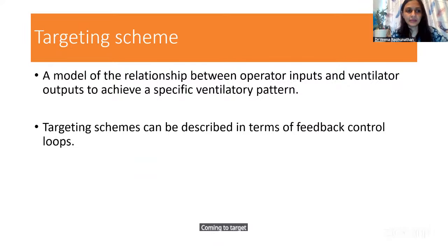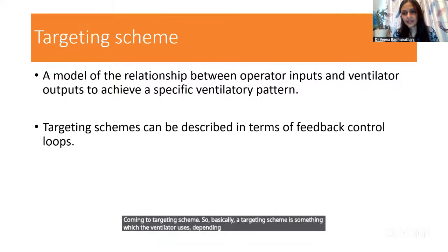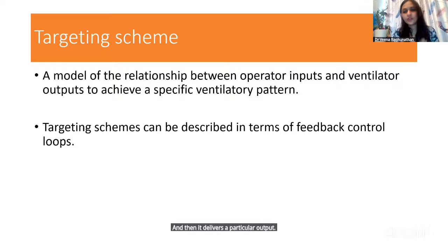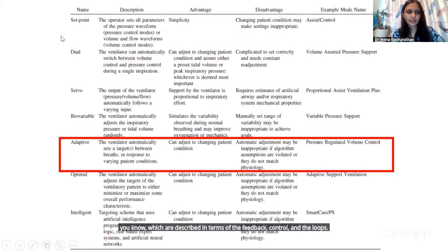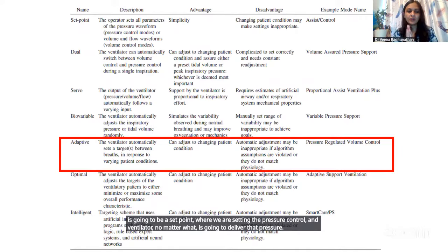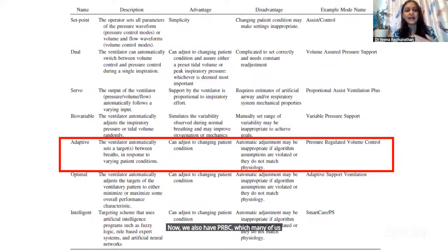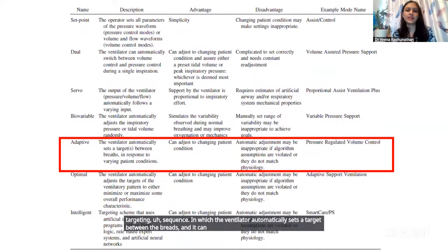Coming to targeting schemes. A targeting scheme is something which the ventilator uses depending on the input it gets, and then it delivers a particular output. The various modes work on various targeting schemes. There are 7 described schemes, described in terms of the feedback, control, and the loops. For example, our pressure control CMV mode is going to be a set point scheme, where we set the pressure control and the ventilator, no matter what, is going to deliver that pressure. Now we also have PRVC, which many of us use, which is an adaptive type of targeting scheme in which the ventilator automatically sets a target between the breaths and can respond to varying patient conditions.